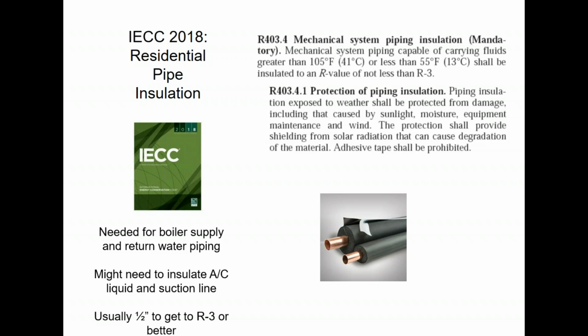If you have radiators, baseboard, or air handlers fed by a boiler, both the supply and return will have to be insulated because they're above 105. If you have a radiant floor, both the supply and return will be between 55 and 105, so you do not have to insulate. If you have a snow melt system, your supply will probably be above 105 and your return will probably be below 55, so you have to insulate both of those. Obviously not the concrete, because that's the radiator, but the piping to it. Hopefully that makes it clear.